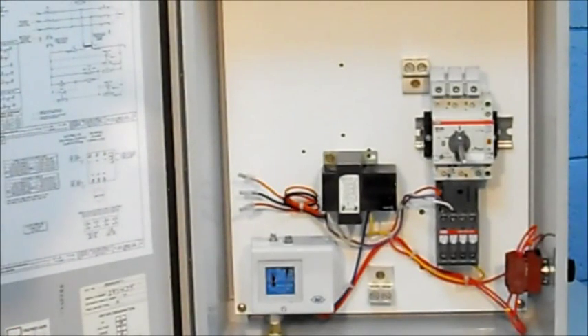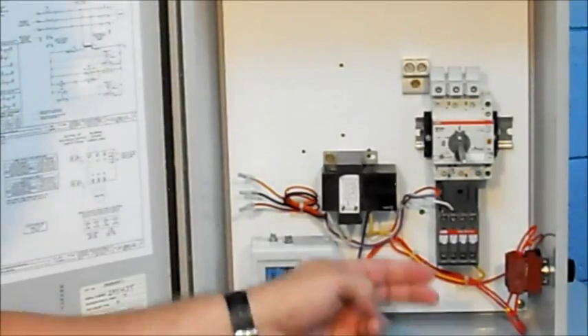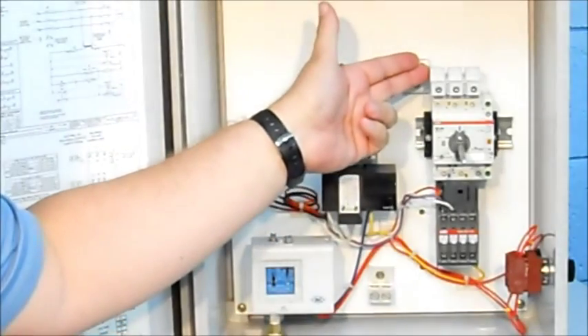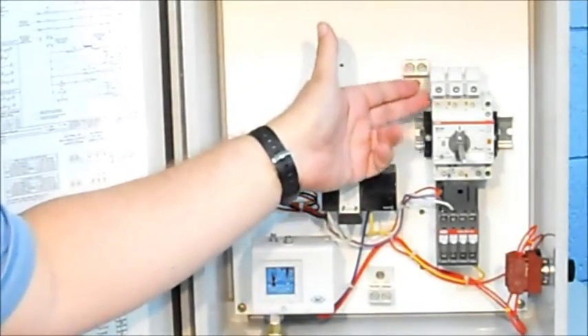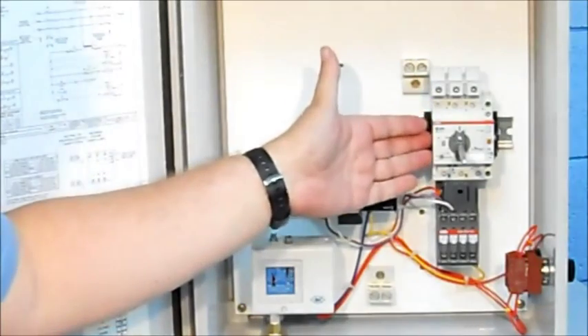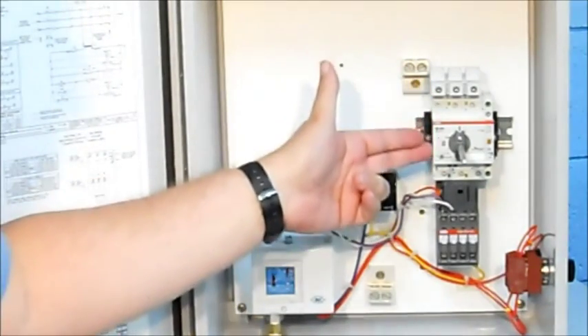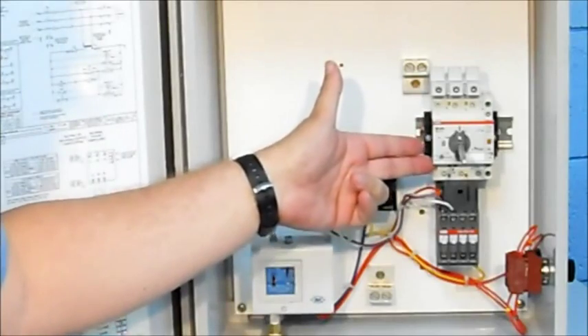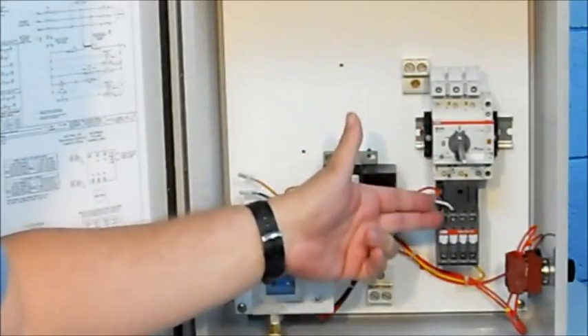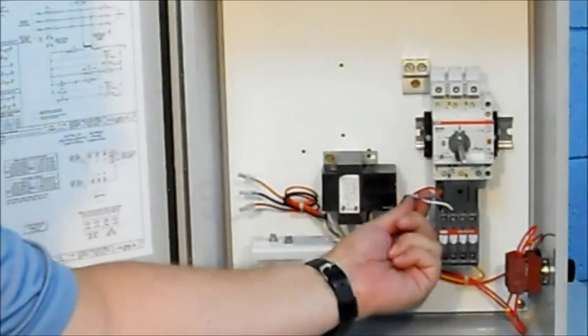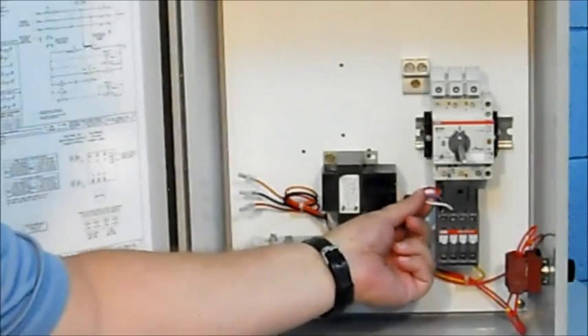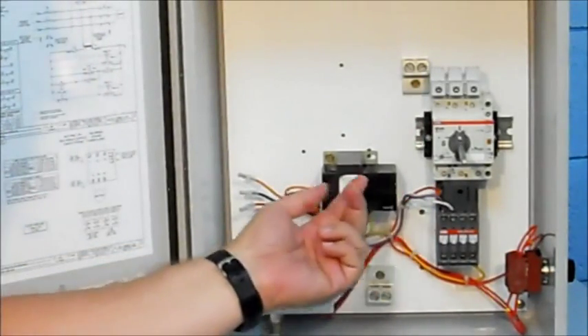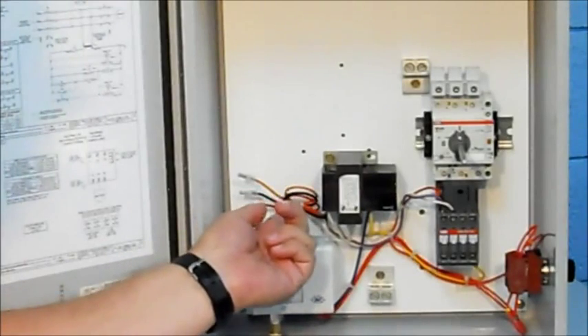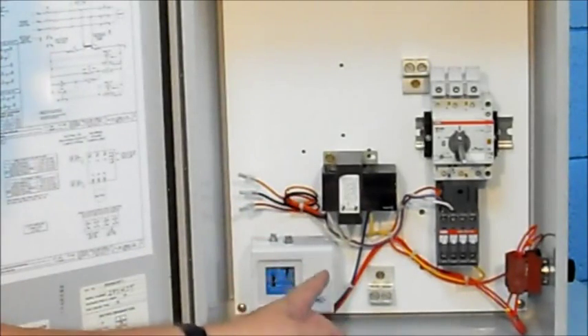Before we can talk about how to troubleshoot, we need to understand how the Jockey Pump Controller works. Power is brought into the Jockey Pump Controller to the top of the isolating switch, disconnect switch here. Goes through the isolating switch, disconnect switch, and into the contactor as well as to the primary side of the control transformer. The power then leaves the secondary side of the control transformer, goes to two places.